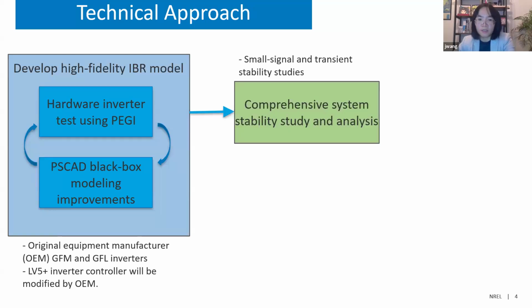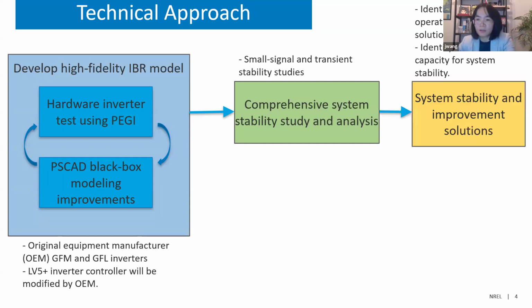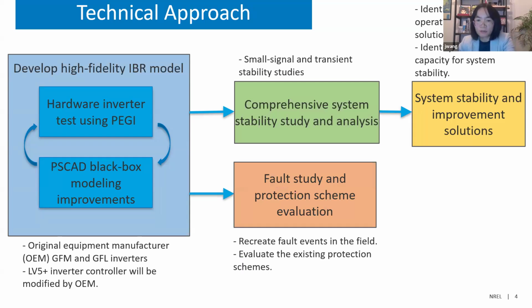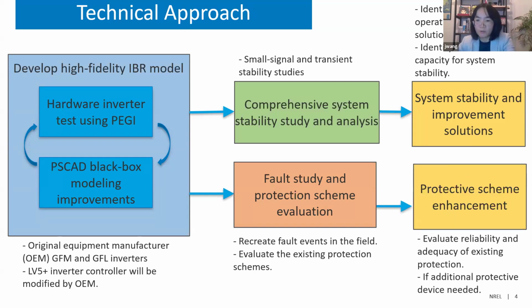And then we move to the stability analysis. We run through the fault ride-through and see how the performance looks. We also do the small signal and the transient stability study to identify the potential challenges and see if grid forming can resolve those challenges. And then we run the fault study and see what the protection challenges are. And then we propose enhancements to increase the protection system reliability. So this is the overall project approach.